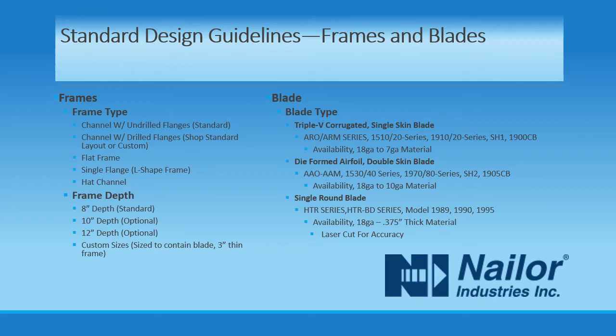On the other end of the spectrum, we can customize the depth of our frame for industrial butterfly dampers to ensure the blade will not protrude out of the frame in any way, resulting in thicknesses of up to 60 inches. In most cases, however, our industrial dampers use an 8-inch deep channel frame with a thickness between 14 gauge and 1/4 inch.